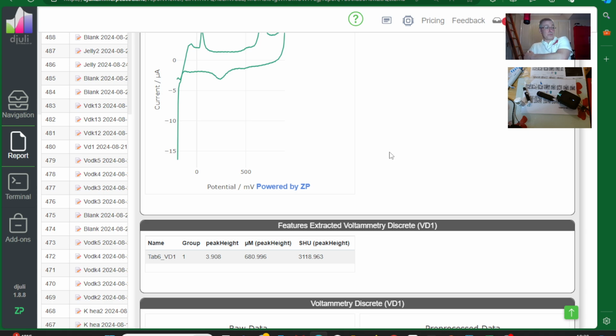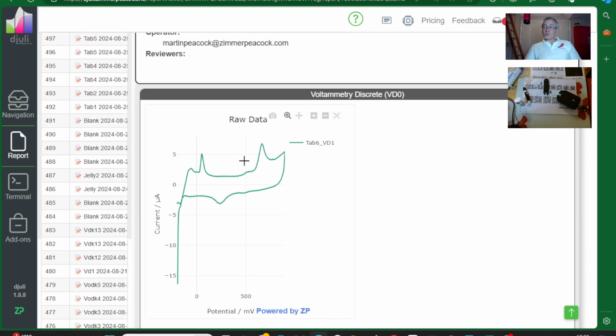The next part of the answer is we don't calibrate regularly, because I started my career making glucose strips, and we were very keen to give a very good user experience. You manufacture sensors, you put the sensors in the meter, you put the sample on there, you get the result. You never ask a diabetic to calibrate with these kind of machines, and we've built the system to be the same way. Does the machine drift, or rather, can you check for it? Because you get the raw signal, we can always see if there's a problem.